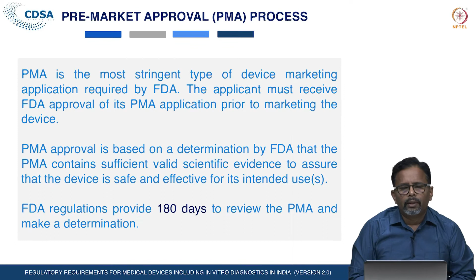The PMA approval is based on the determination by the FDA that the PMA contains sufficient valid scientific evidence to assure that the device is safe and effective for its intended use. The FDA regulation provides 180 days to review the PMA applications and to make the final decision. 180 days have been given for review of the PMA application by US FDA, and the regulation governing the pre-market approval is prescribed in Title 21 Code of Federal Regulations, CFR Part 814, pre-market approval.